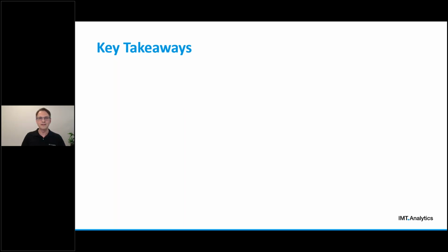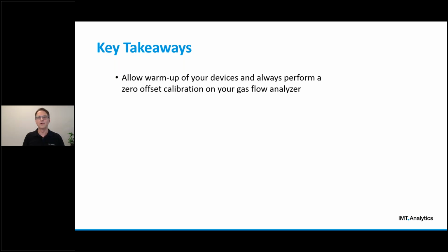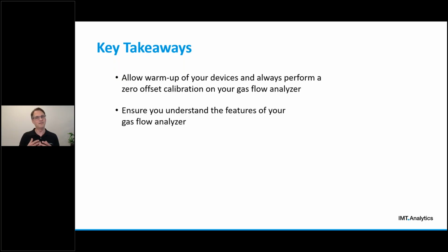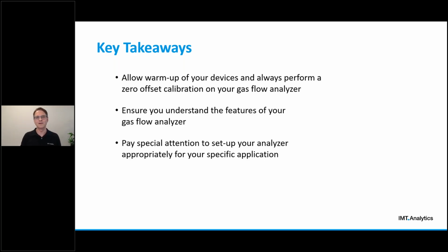So number one key takeaway is ensure that you allow warm-up of your analyzer and your device under test, and after that perform a zero offset calibration on your gas flow analyzer before you start taking measurements. Number two is that you need to understand the features of your gas flow analyzer. So be aware what is measured inside the flow channel, for example, and what not, and make sure that you understand the setup related considerations for your specific device. Number three is to pay special attention to have the appropriate settings on your analyzer for your specific application. As you've learned in this session, this is very important.